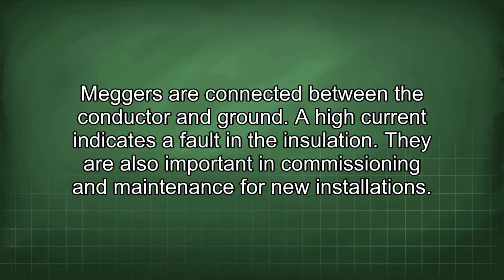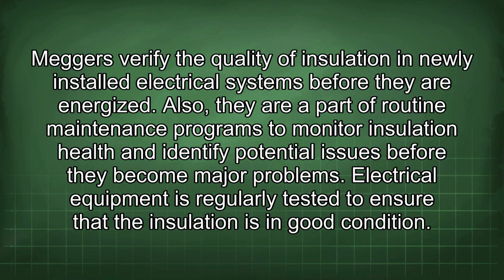Meggers are connected between the conductor and ground. A high current indicates a fault in the insulation. They are also important in commissioning and maintenance for new installations. Meggers verify the quality of insulation in newly installed electrical systems before they are energized. Also, they are part of routine maintenance programs to monitor insulation health and identify potential issues before they become major problems. Electrical equipment is regularly tested to ensure that the insulation is in good condition.